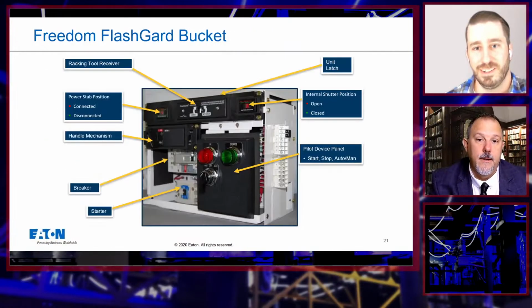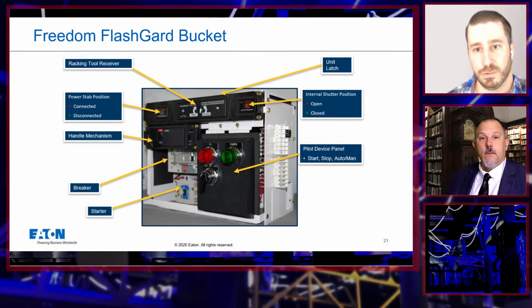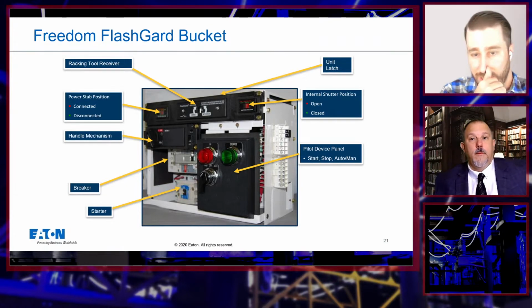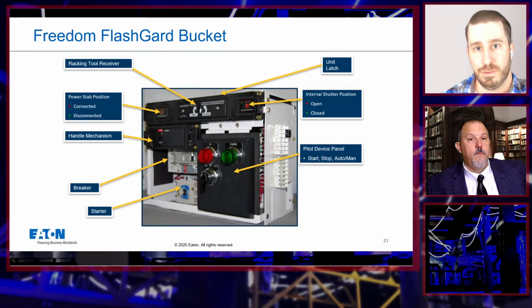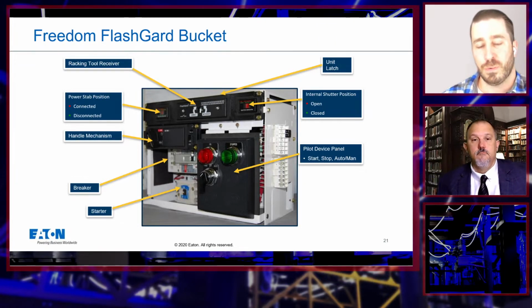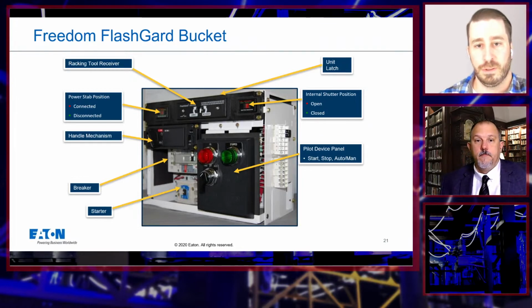And be able to rack it out, right? This is one of the things you'll see in NFPA 70E - if you have arc resistant equipment construction and an ability to rack a unit out from a motor control center, your likelihood of exposure greatly decreases. Because all the doors are completely secured, and you're removing it from power, you're not likely to experience exposure there.